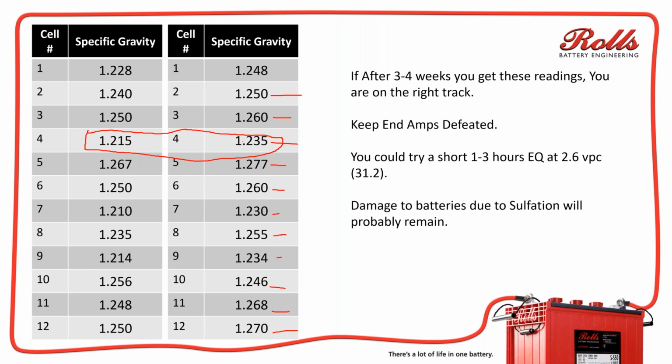Don't just continually hit the battery bank with a hard equalization every day. I get customers that call up and say, Steve, I equalized my battery bank 6 times in the last 3 days and it still hasn't recovered. Well, it's probably not going to, and you're actually causing more damage to the batteries than you are helping. So you have to be patient when you're doing this troubleshooting.